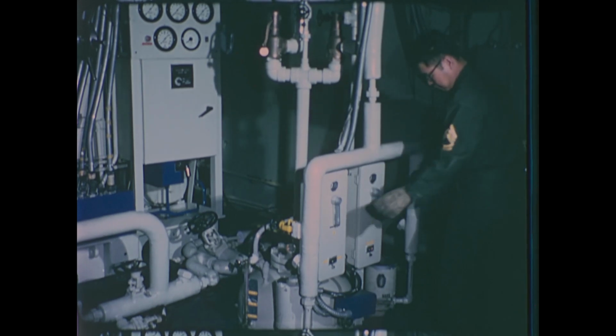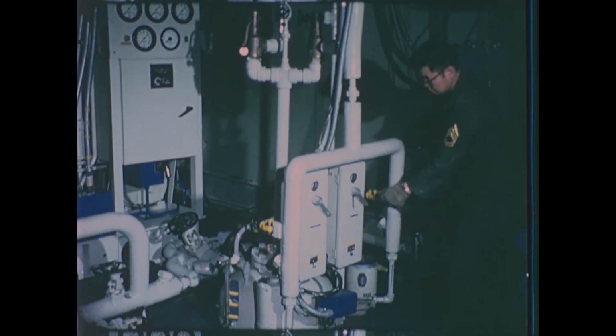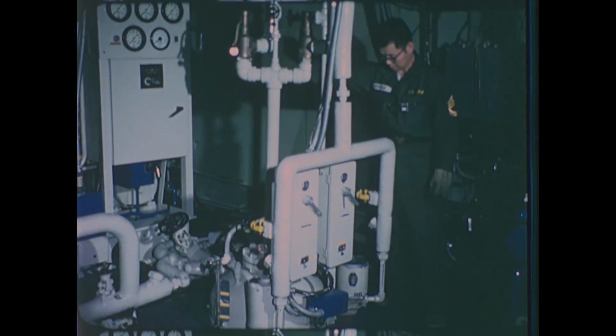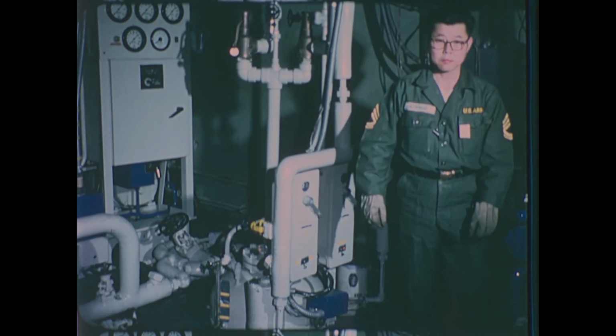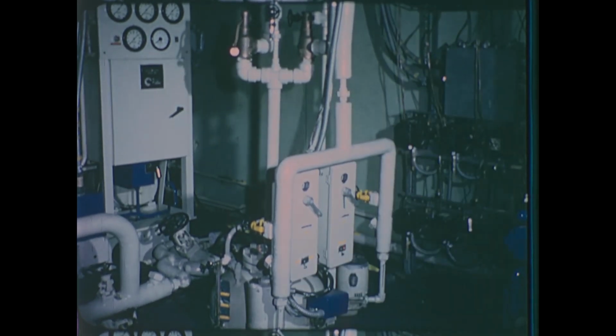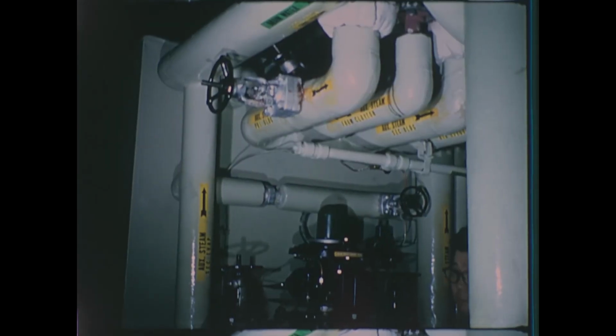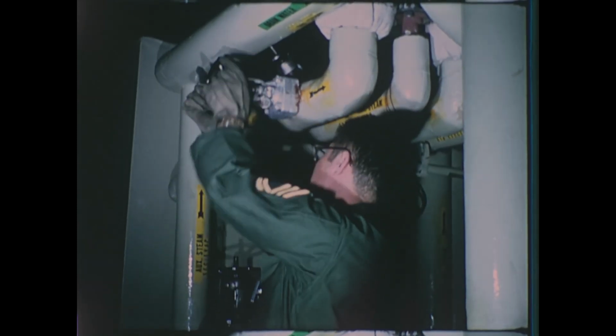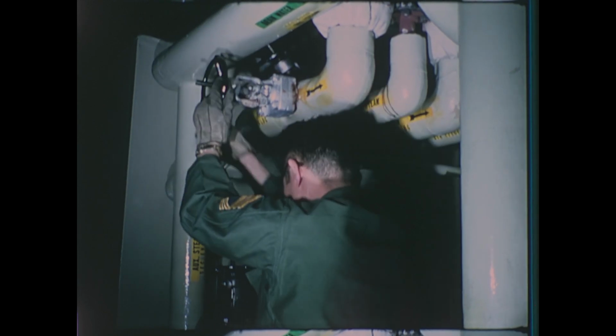The turbine drain tank system, including pump breakers, are lined up to receive and transfer the condensate from the turbine to the hot well. Now the main steam line will be warmed up using the main steam stop bypass valve. The equipment operator lines up the auxiliary steam line from the pressure regulator to the primary building and closes the valve from the auxiliary boiler.